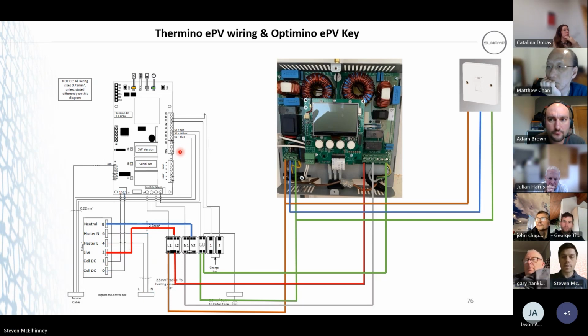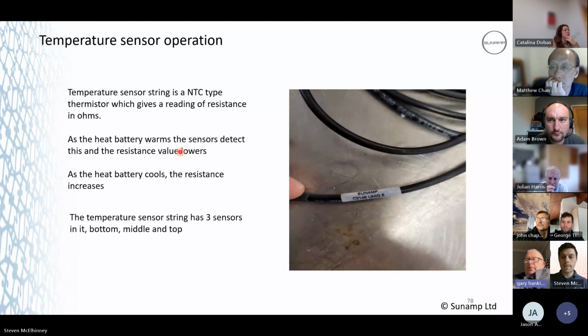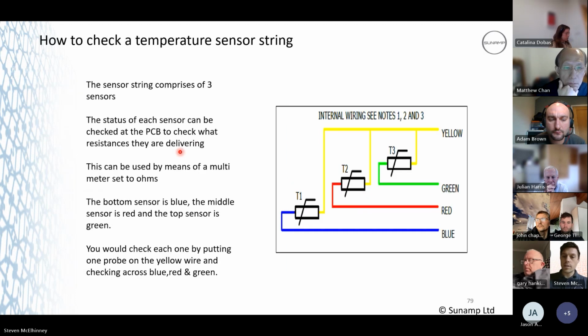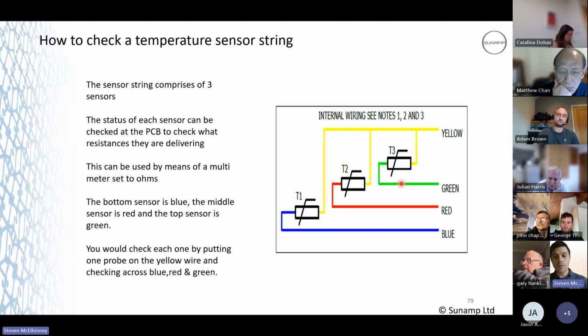So what's the resistance, Steve? At ambient temp, about 12 kiloohms, I think, when it's cold. If it's up to temperature, that's going to be about 1.4 kiloohms. This will be about 1.5, 1.6, and this will be about 1.6, 1.7 when it's up to temp. Okay, thank you. So this is actually a good way.